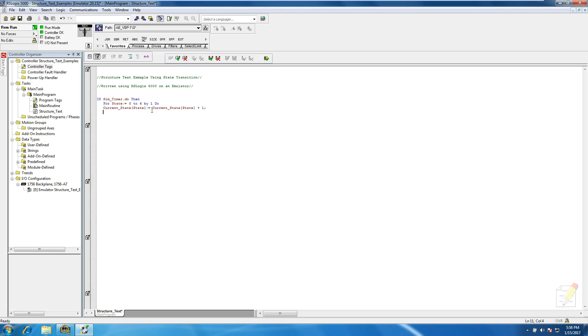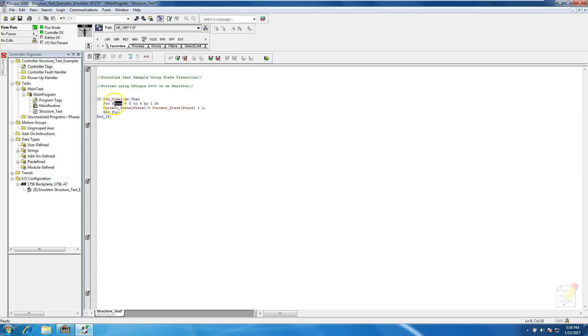Now we close our END_FOR - remember you have to put your end marks - and then we close our END_IF. What this is going to do is every time the timer goes done, it is going to index the state from zero to six by one, taking the current state value.